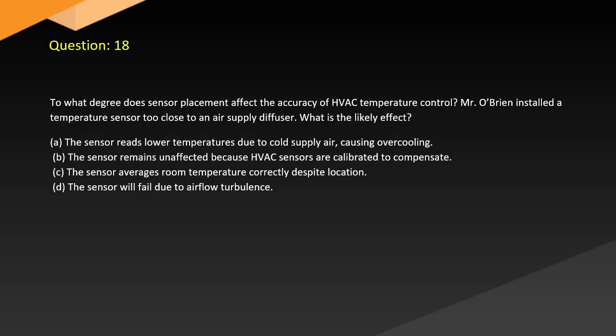Question 18. To what degree does sensor placement affect the accuracy of HVAC temperature control? Mr. O'Brien installed a temperature sensor too close to an air supply diffuser. What is the likely effect? A. The sensor reads lower temperatures due to cold supply air, causing overcooling. B. The sensor remains unaffected because HVAC sensors are calibrated to compensate. C. The sensor averages room temperature correctly despite location. D. The sensor will fail due to airflow turbulence.